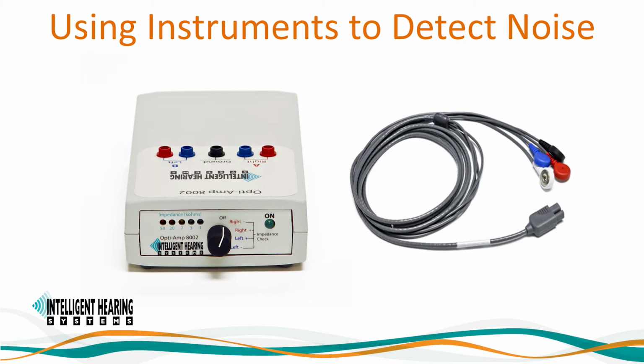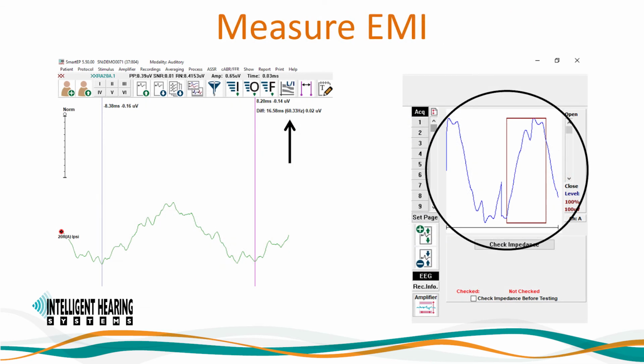For users of the OptiAmp transmitter, simply turn on the transmitter and move it around the room and view the incoming EEG for all channels. For Duet users, you can move the Duet box around and evaluate the input signals from your environment on the EEG display window. You can also place the patient cable and the electrode leads at the site of testing and analyze the EEG. Avoid testing at places where the electrical noise shows high amplitude or saturating EEG, cyclical EEG, large spikes, or other EEG anomalies that are not the desired low amplitude, steady EEG typically viewed when a patient is calm and sleeping.